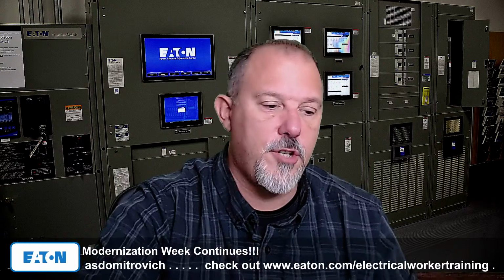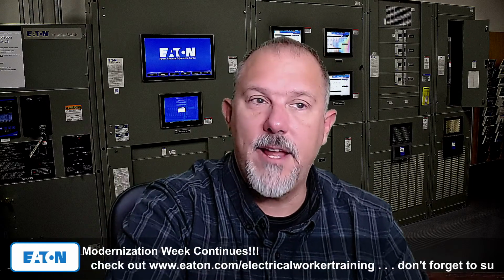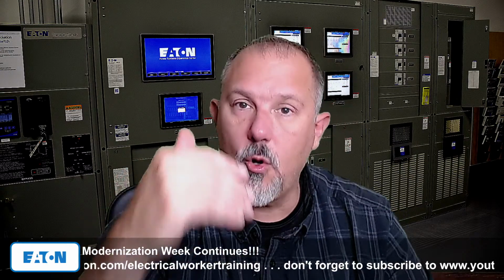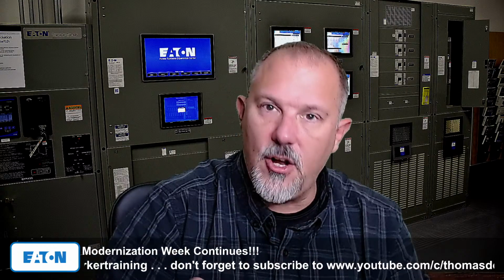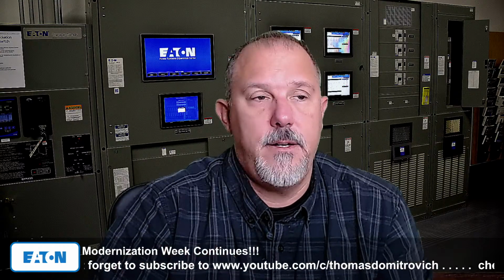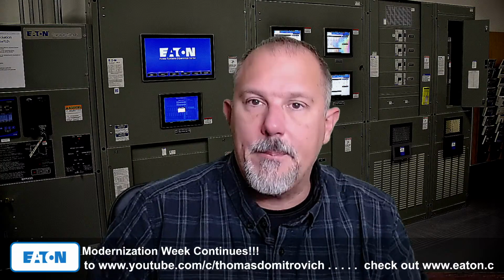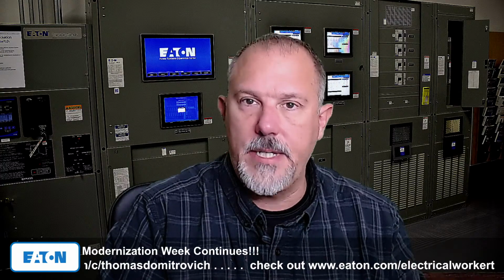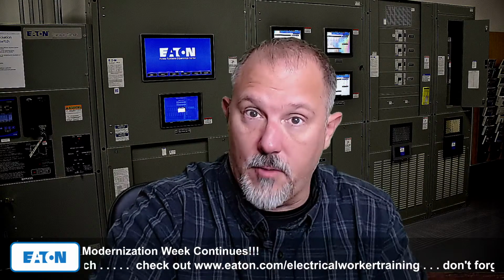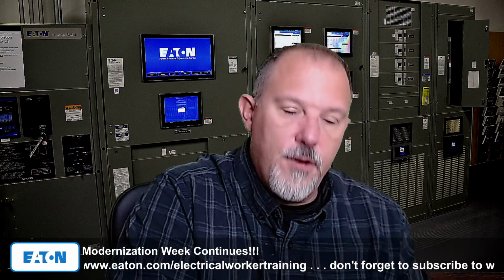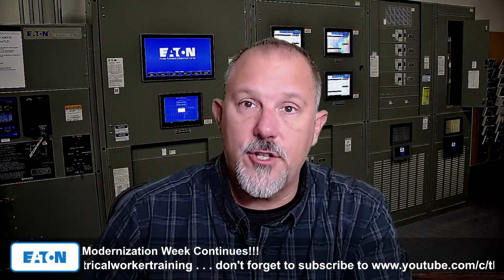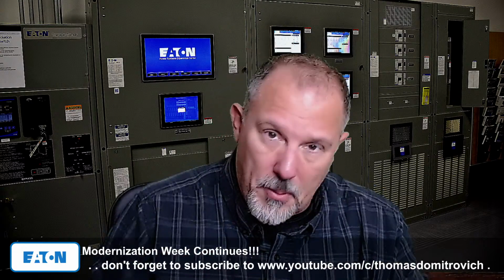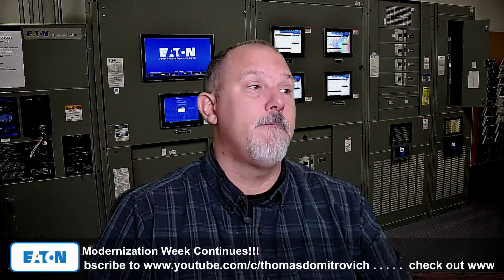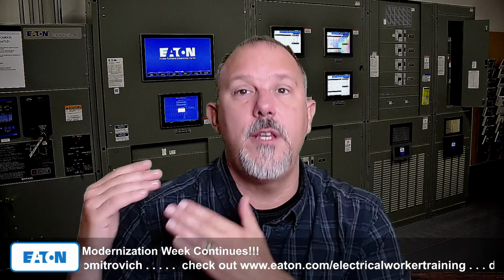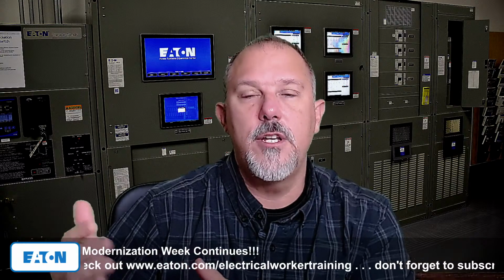You know what, David? You are right. And there should be limitations because some of these might be high frequency leakage currents. I don't have to shunt those leakage currents to the neutral or to the equipment grounding conductor. If I required a neutral, I can use that neutral to bleed off any of those currents that I need. Say it's an adjustable frequency drive or whatever. If I am going to put caps in to filter things inside my unit for whatever reason, I'd rather do that to the neutral than the equipment grounding conductor. But again, that takes a design change of the HVAC unit. It takes probably a change in the National Electrical Code, although I'd argue that if the instructions for the unit said pull a neutral, you'd be pulling a neutral, right? I mean, look at what we did with dryer circuits and whatnot. Look at what we did with the light switch, where they were using the equipment grounding conductor to power electronics inside of these occupancy sensors.